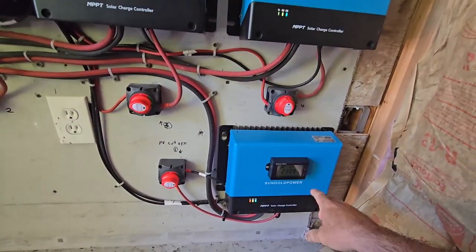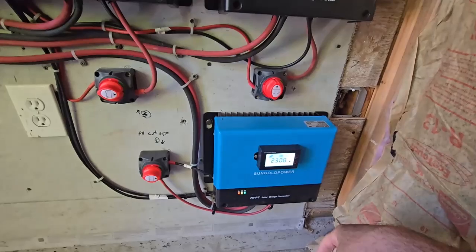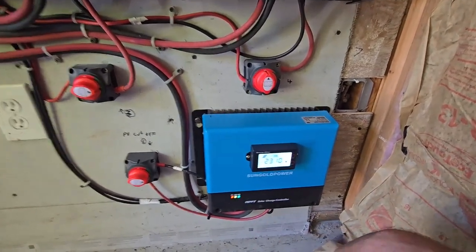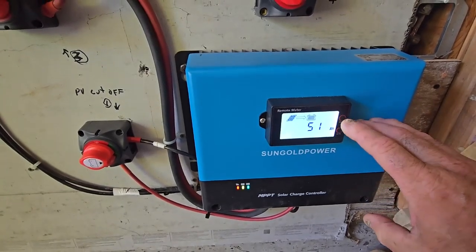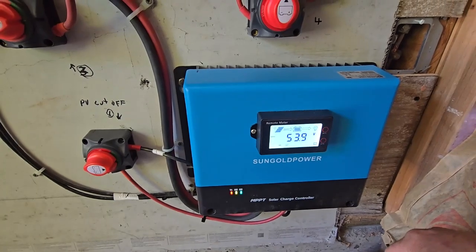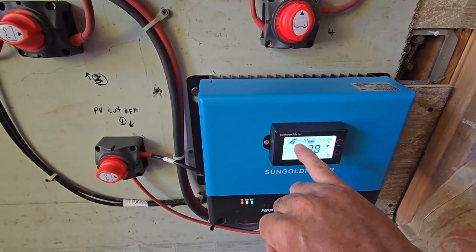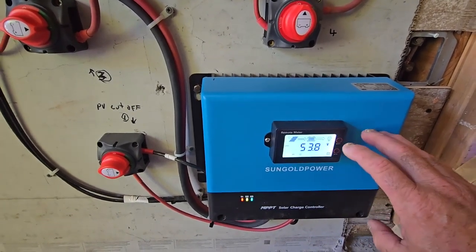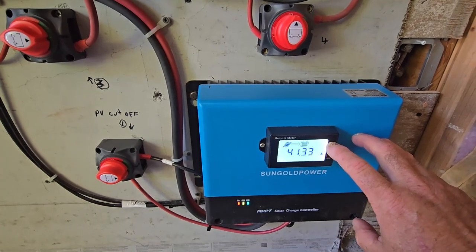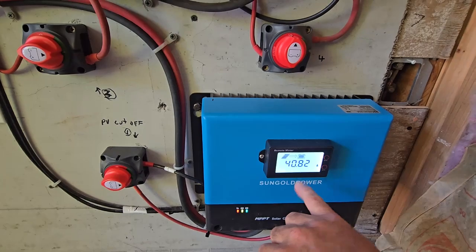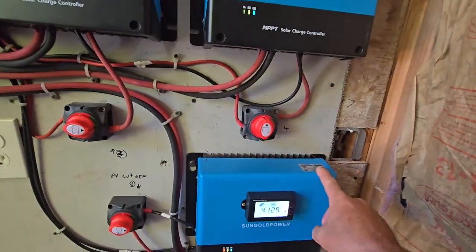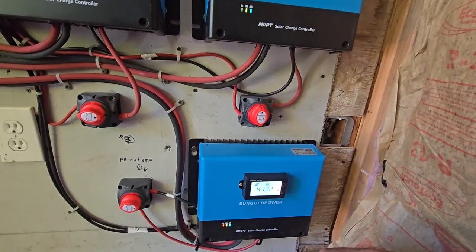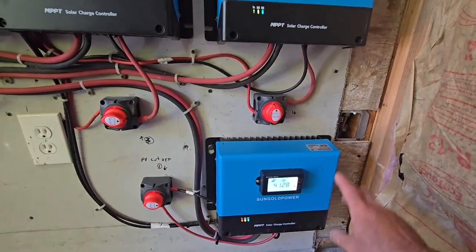So right now, number one has eight panels on it. It's like 9 o'clock in the morning, and it's producing 2,300 watts DC power. And scroll through. It says the batteries are at 53 volts. It shows the solar panel is charging the batteries. The batteries are then powering the load. So it says this machine is producing 41 amps, DC amps, right now. It's not warm yet, but during the heat of the day, this will start reducing the power it lets go through to the battery. So the batteries are probably about a quarter charged, maybe half charged right now.